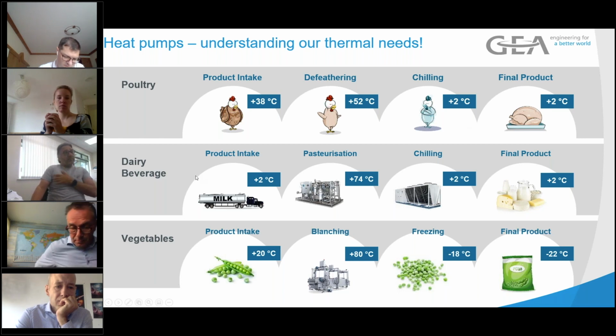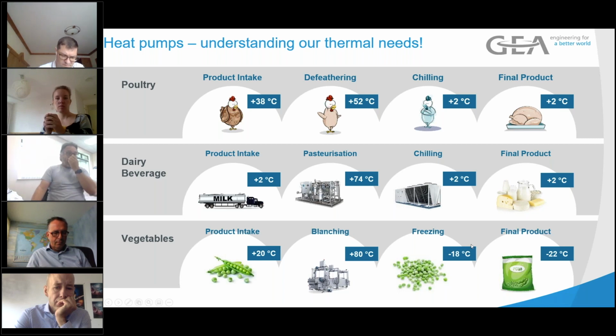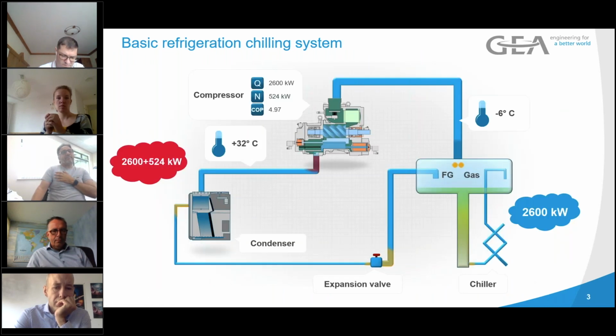Likewise, in the milk side, the milk goes in, hopefully at 2, gets pasteurized, the refrigeration guys go and chill it, and then again it goes to storage and cold distribution. Vegetables, as an example, they come off the field, they get blanched, washed around 80 degrees, and normally they go off for freezing. So you can see all of the heat going in via a boiler, and then the heat being removed again via the refrigeration process.